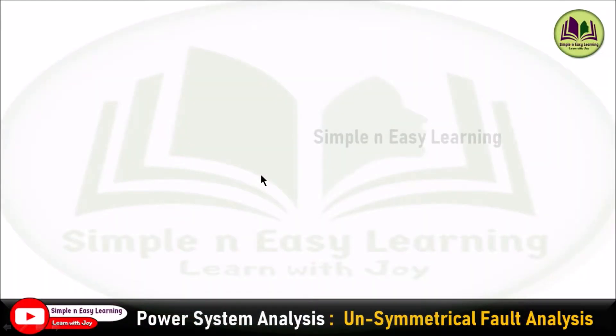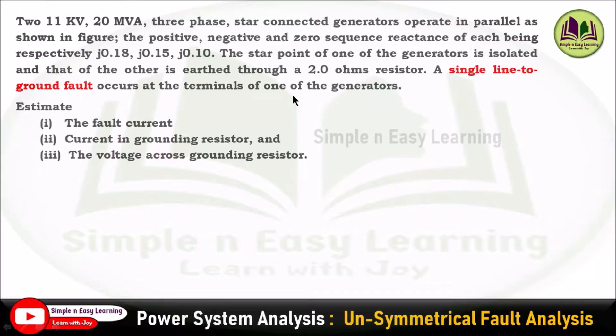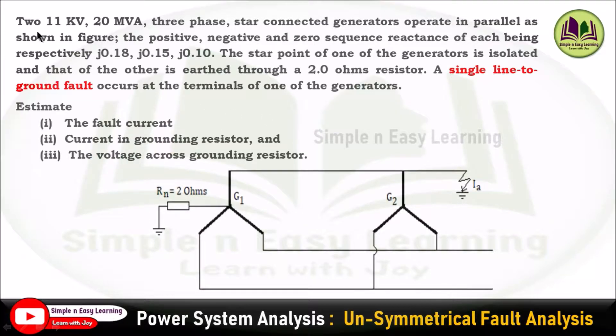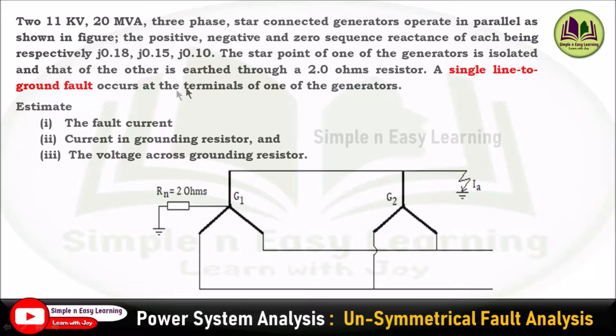Unsymmetrical fault analysis: solved problem based on single line to ground fault. Consider the given problem: two 11 kV, 20 MVA three-phase star-connected generators operating in parallel. The positive, negative, and zero sequence reactances of each are J0.18, J0.15, and J0.10 respectively. The star point of one generator is isolated and that of the other is grounded through a 2 ohm resistor. A single line to ground fault occurs at the terminals of one of the generators. Estimate the fault current, the current in the grounding resistor, and the voltage across the grounding resistor.